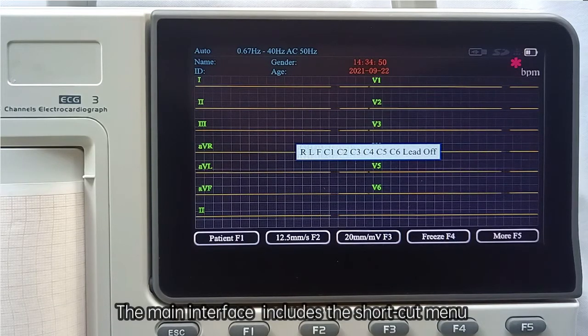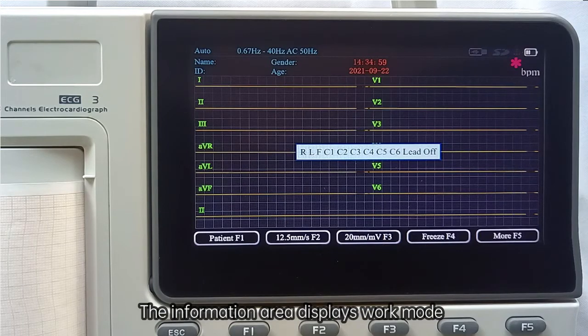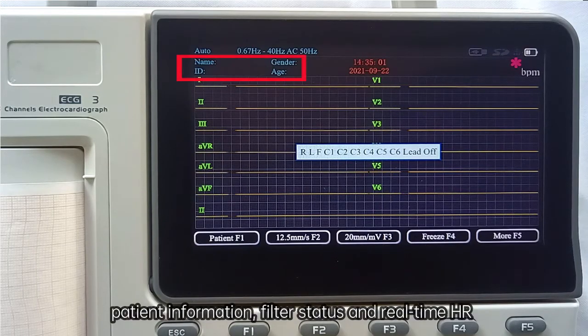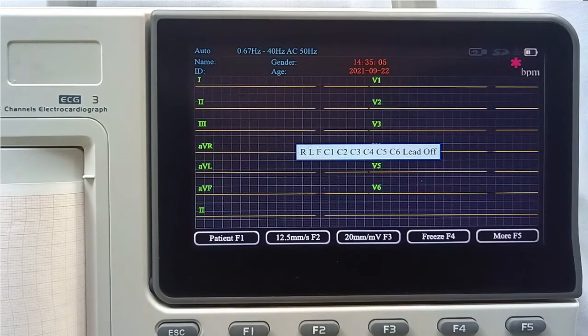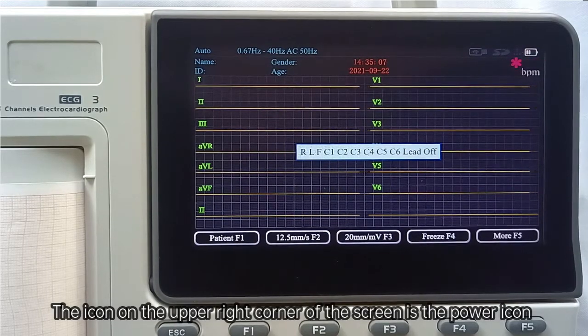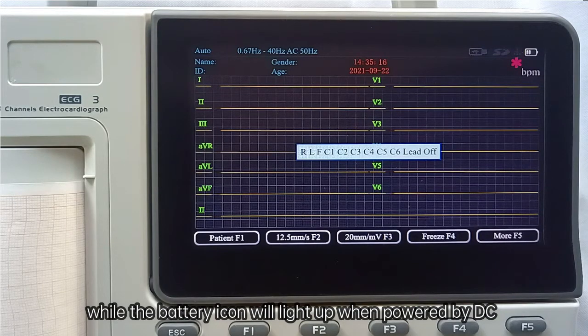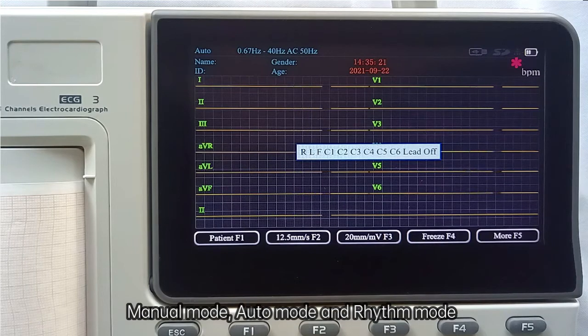The main interface includes the shortcut menu, waveform display area, and information display area. The information area displays work mode, patient information, filter status, and real-time heart rate. The icon in the upper right corner is the power icon — the charge icon lights up when powered by AC, while the battery icon lights up when powered by DC. The available modes are manual mode, auto mode, and rhythm mode.